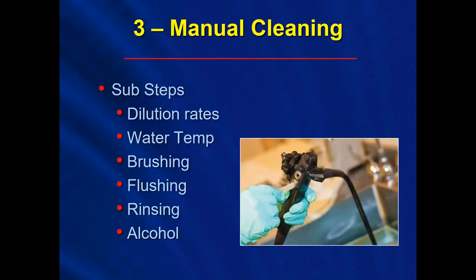Now, step 3 is the manual cleaning process, again with the sub-steps. The manual cleaning process takes place after bedside cleaning and after leak testing, and is a key step in reducing the risk of cross-contamination. Probably the second most important step. This step will further decrease the bioburden load and reduce the risk of biofilm development.